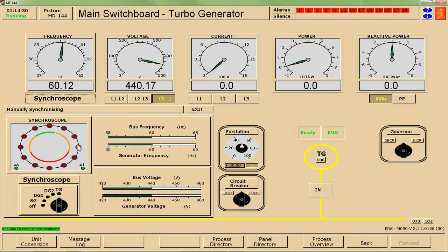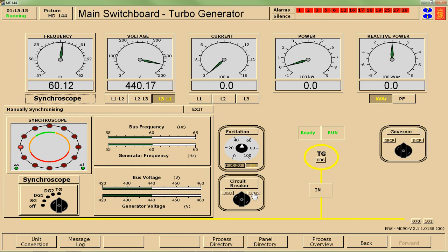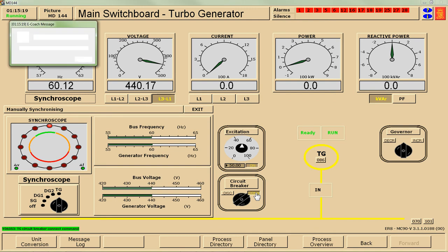Now what I have to do is wait for the timing of that frequency to be the same as the grid. The timing for when I connect is indicated by when this red dot gets into the green zone. I'm generally waiting to hit the 11 o'clock position with a red dot that's moving clockwise, and when I do, I'm going to connect with my circuit breaker. I'll wait for my red dot to get into the green zone — at the 11 o'clock position — and I've hit connect.